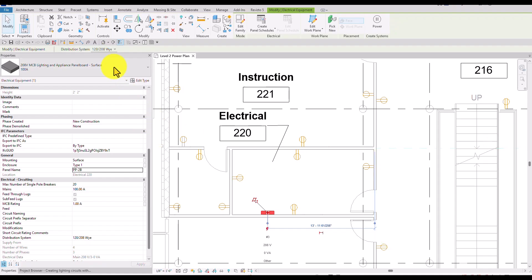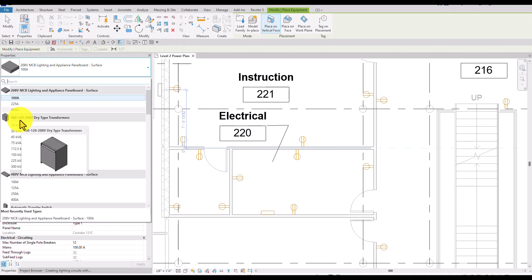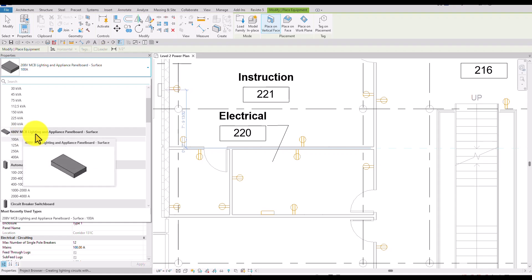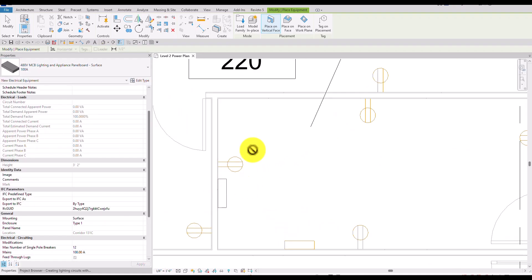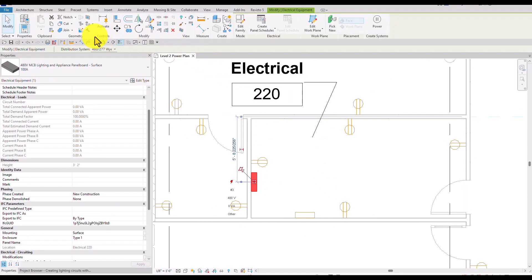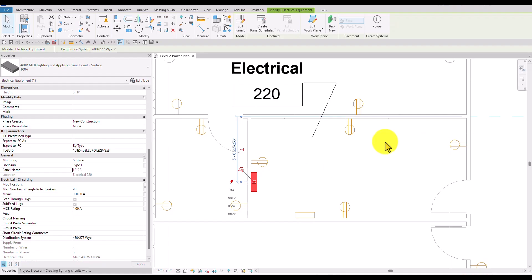Next, I'll repeat the same procedure but this time select Electrical Equipment with the 480-volt MCB — Lighting and Appliance Panel Board, Surface. I'll select 100 amps again and place it on the wall with Vertical Face selected. After selecting Modify, this panel has a different distribution system: 480/277Y. I'll set the maximum number of pole breakers to 20 and name this panel 'LP-2B' for the lighting panel.